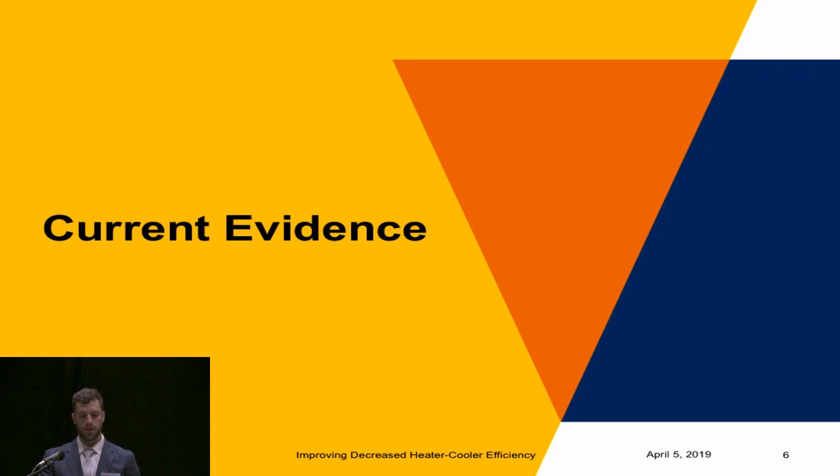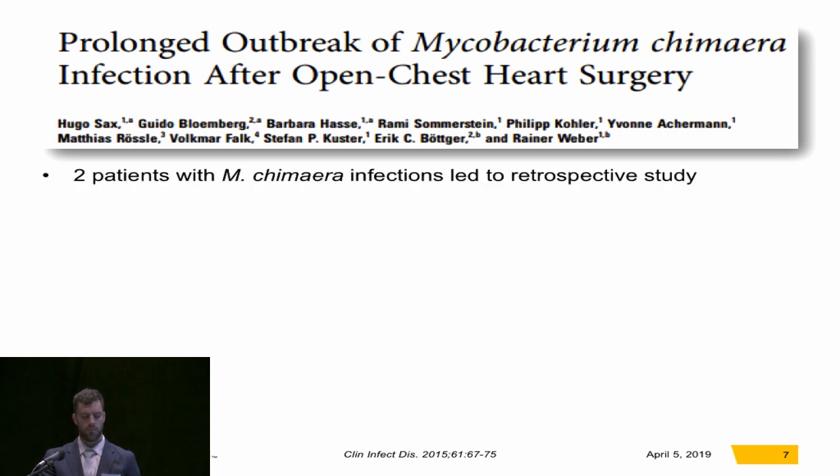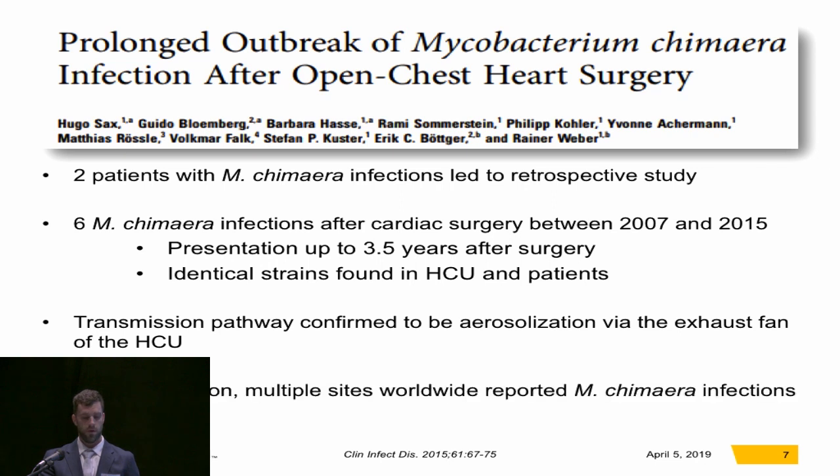The current evidence linking the heater cooler to this bacteria: in 2015, Sachs and colleagues in Europe came out with a study. Two patients with M. chimaera led to a retrospective study at their institution. What they found was that between 2007 and 2015, they actually had six M. chimaera infections after cardiac surgery. The presentation after surgery was up to three and a half years, and they found identical strains in the heater cooler as well as the patients. They confirmed the pathway to be aerosolization via the exhaust fan of the heater cooler. After this publication, there was a whirlwind, and multiple sites worldwide reported M. chimaera infections.